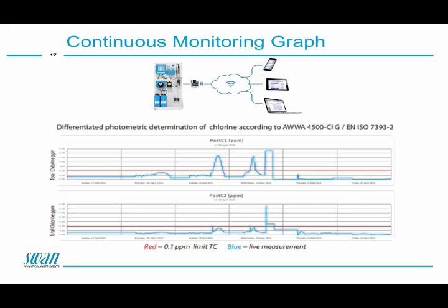Sometimes I understand what you're saying. So sometimes what happens is the carbon 1 has so much chlorine that it's exhausted, and there's breakthrough through the carbon 2 as well. So in the first instance, what you probably have seen is that the carbon 1's been exhausted. It's allowed some chloramine through, but the carbon 2 has caught that extra chloramine. However, the second day, because that carbon 2 was catching that chloramine, it's allowing more through the second day when there's that slug. Does that make sense?